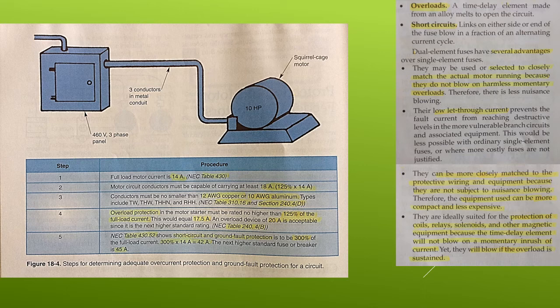Dual element fuses. Dual element fuses are designed mainly for motor circuit protection. The fuse blows and opens the circuit when either of two elements inside opens. This occurs during the following circuit faults: overloads, as you can see on the right side of the screen, a time delay element made from an alloy melts to open the circuit; short circuits, links on either side or ends of the fuse blow in a fraction of an alternating current cycle.